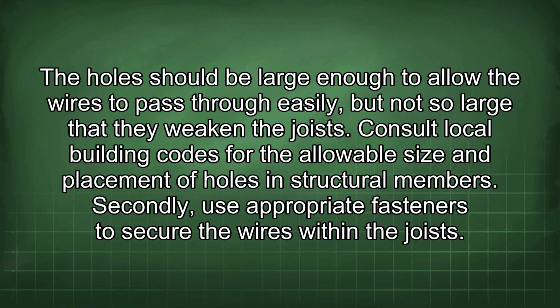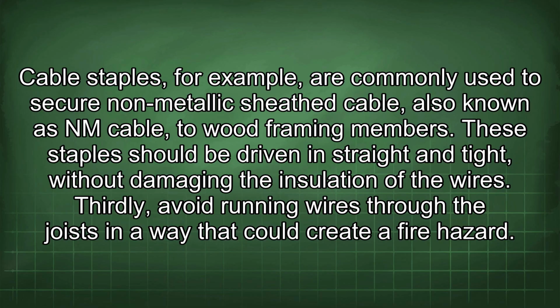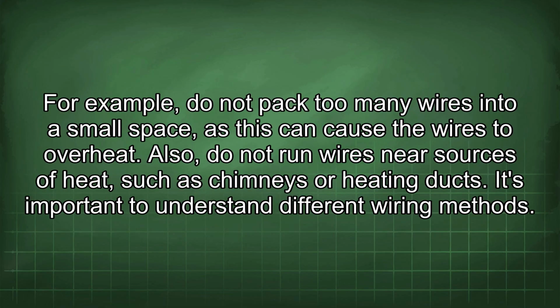Secondly, use appropriate fasteners to secure the wires within the joists. Cable staples, for example, are commonly used to secure non-metallic sheath cable, also known as NM cable, to wood framing members. These staples should be driven in straight and tight without damaging the insulation of the wires. Thirdly, avoid running wires through the joists in a way that could create a fire hazard. For example, do not pack too many wires into a small space, as this can cause the wires to overheat. Also, do not run wires near sources of heat, such as chimneys or heating ducts.